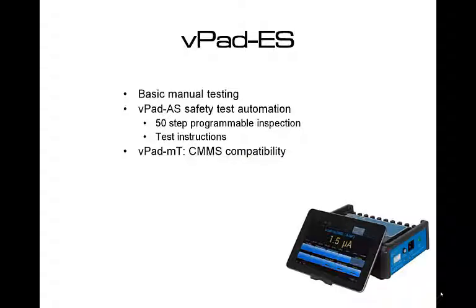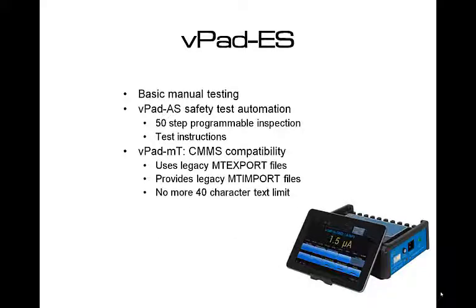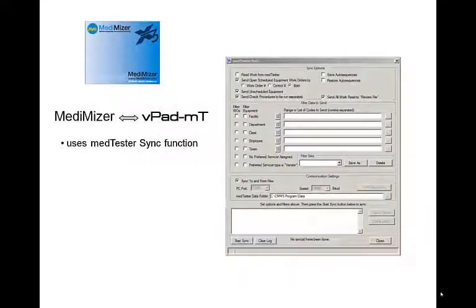VPAD MT uses the legacy MedTester MT export files to define the safety and performance tests, and imports the test results with the legacy MT import files. VPAD MT does not have a 40-character check instruction line limit and can display the full 75-character lines that can be input into Medimizer. Exporting the PM schedule to VPAD follows the same process as you are used to with Medimizer.